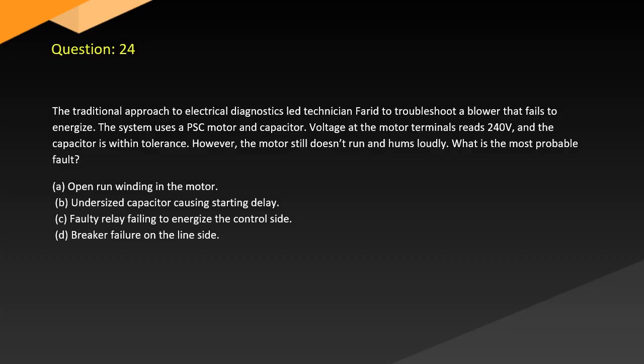Question 24. The traditional approach to electrical diagnostics led technician Farad to troubleshoot a blower that fails to energize. The system uses a PSC motor and capacitor. Voltage at the motor terminals reads 240 volts and the capacitor is within tolerance. However, the motor still doesn't run and hums loudly. What is the most probable fault? A. Open run winding in the motor. B. Undersized capacitor causing starting delay. C. Faulty relay failing to energize the control side. D. Breaker failure on the line side.